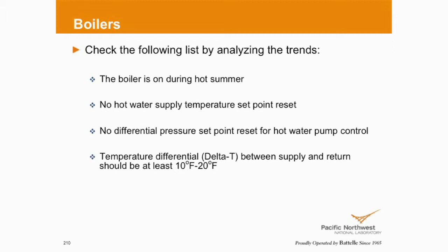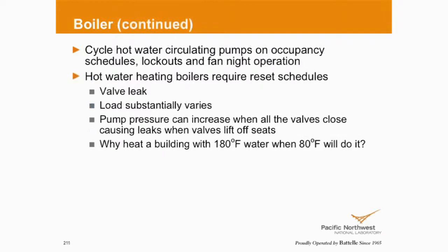What should we see on a properly sized boiler that's running for the appropriate load? 10 to 20 degrees. What do we typically see? If it's not, 2 to 4 degrees. So those are some numbers out of industry. So we talked about circulating pumps. Can we keep the boilers hot but shut off the circulating pumps? Depends on what your design is. You might be able to do that.